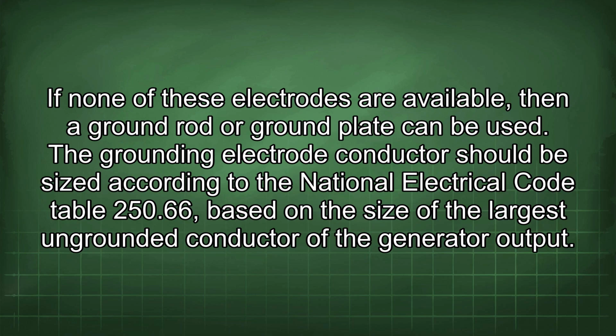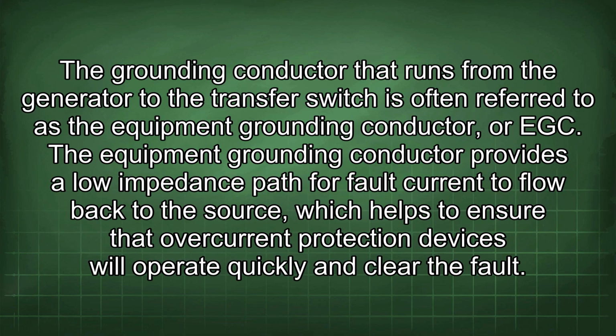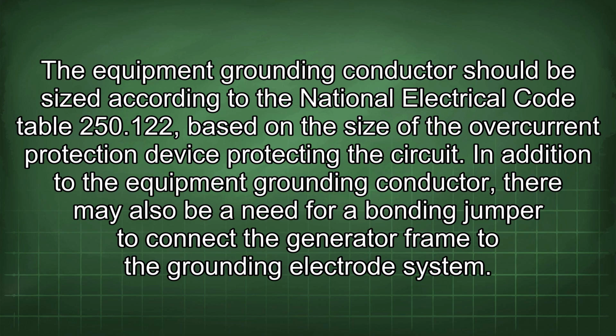The grounding electrode conductor should be sized according to the National Electrical Code Table 250.66, based on the size of the largest ungrounded conductor of the generator output. The grounding conductor that runs from the generator to the transfer switch is often referred to as the equipment grounding conductor, or EGC. The equipment grounding conductor provides a low impedance path for fault current to flow back to the source, which helps to ensure that overcurrent protection devices will operate quickly and clear the fault. The equipment grounding conductor should be sized according to the National Electrical Code Table 250.122, based on the size of the overcurrent protection device protecting the circuit.